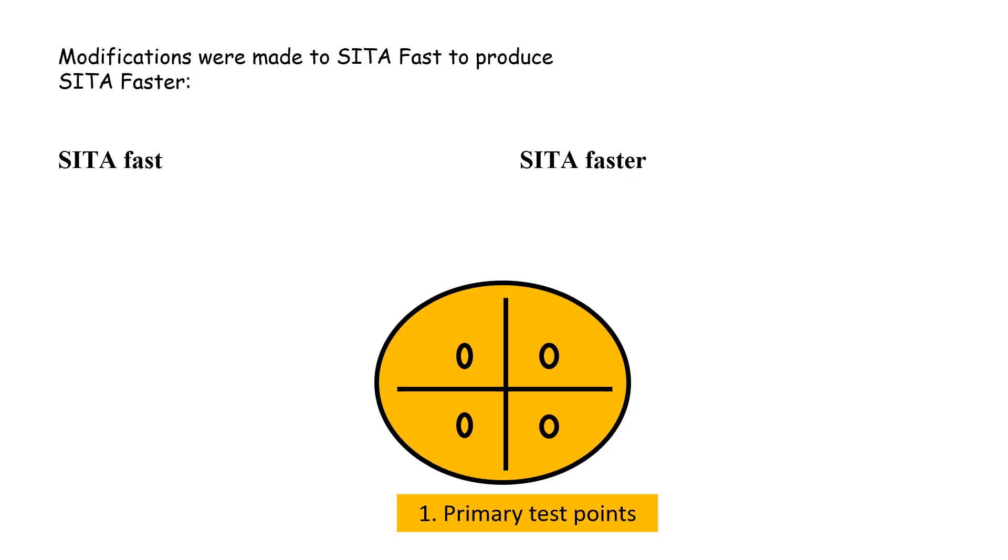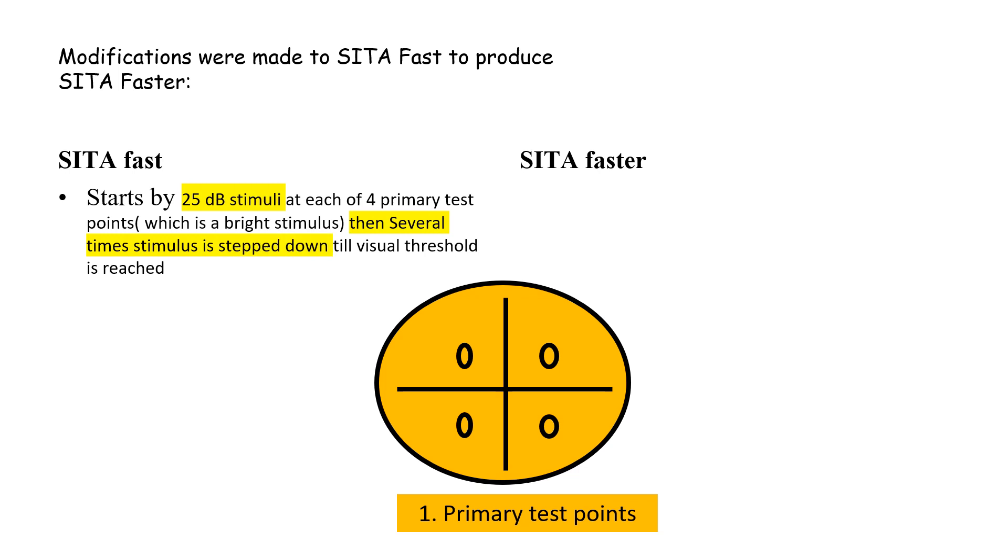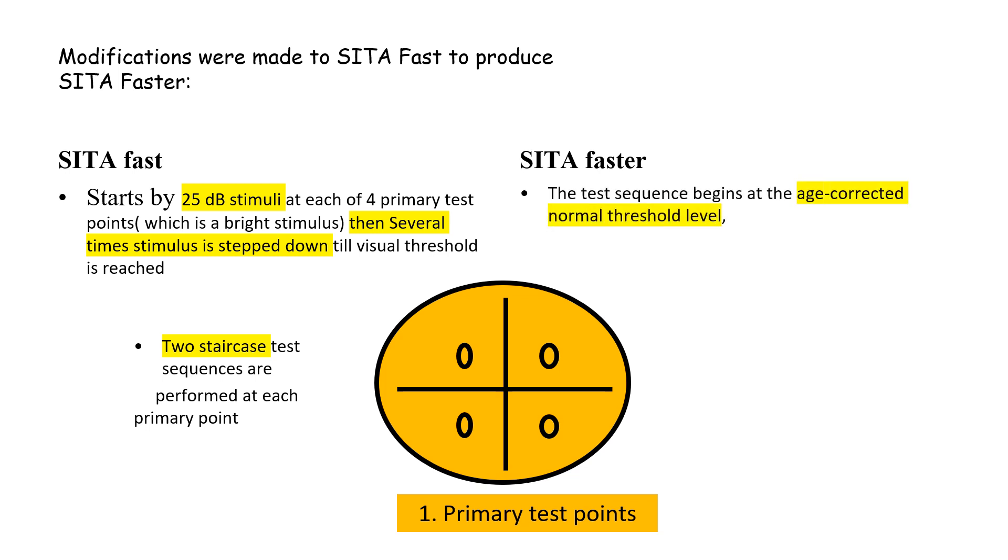Shorter test duration is achieved through several mechanisms. First, the primary test locations in SITA Fast start with a 25 decibel stimulus and then step down until threshold is reached. Two staircase test sequences are performed at each of the primary points. In SITA Faster, the test sequence begins at the age-corrected normal threshold, and only one staircase reversal is required.